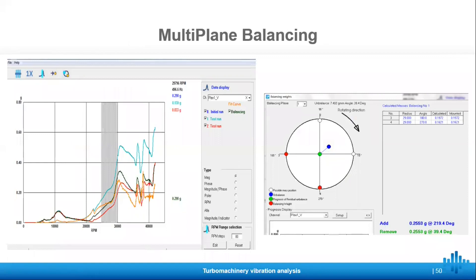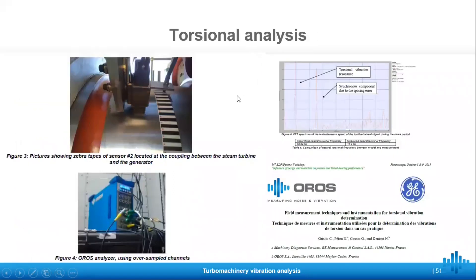If the machine is tripping due to high vibration levels, this tool is used to balance the rotor by telling us where to add mass and how much mass to add in order to minimize these vibration levels and get the rotor as balanced as possible. Now, to wrap up these other tools, we will quickly cover torsional analysis. Torsional analysis is especially useful for turbines that are subjected to new components as renewable energy becomes more and more popular.